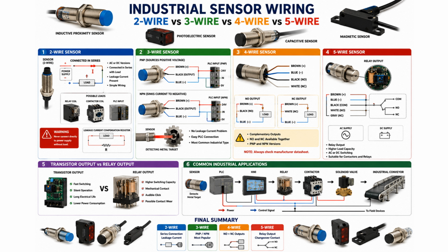Final summary. When you pick up a sensor, the number of wires is not just a physical characteristic. It provides very important information about the output type, the wiring method, the type of load that can be connected, compatibility with a PLC, operating speed, and its industrial applications. If you learn these concepts correctly, you will be able to make much more accurate and professional decisions when designing electrical panels, troubleshooting industrial machines, and programming PLC systems.